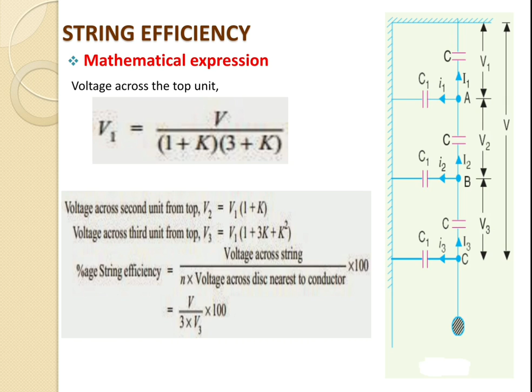whereas the voltage across the discs decreases as we reach the cross arm. Second point is that the greater the value of K, that is K equal to C1 by C, the less uniform is the potential across the discs and the lesser is the string efficiency. Third point from the above equation is that the inequality in the voltage distribution increases with the increase in the number of discs in the string. Therefore, a shorter string has more efficiency than a larger one. So these are some of the points that we get from the above expression.